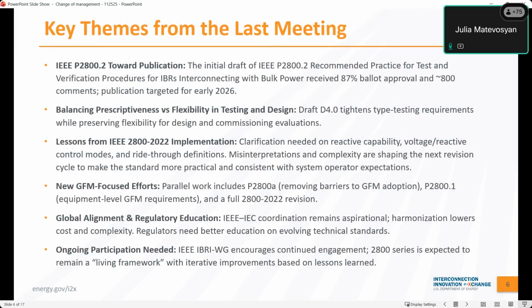So just a few key themes from the last meeting. IEEE 2800 is progressing towards publication. The initial draft of the document received 87% ballot approval, and we got 800 comments to address. Primarily, the comments were about unit level testing and design evaluation, and we addressed the comments, reballoted it, and the ballot received 95% approval. So it happened after the meeting, but just to provide this update.